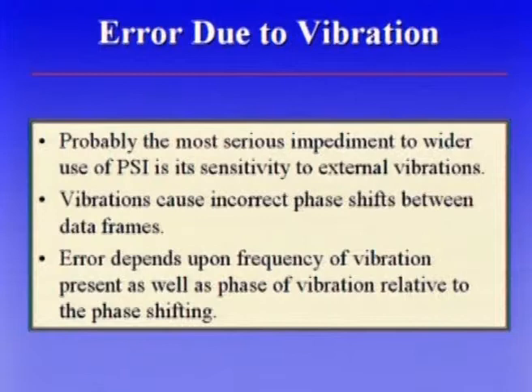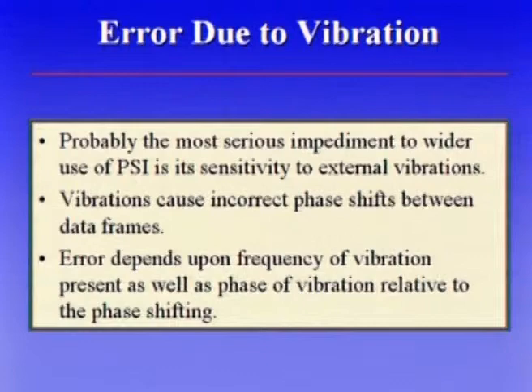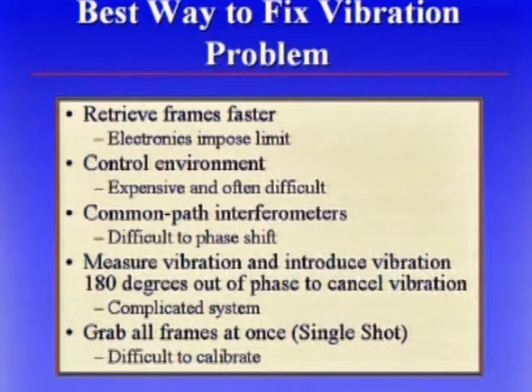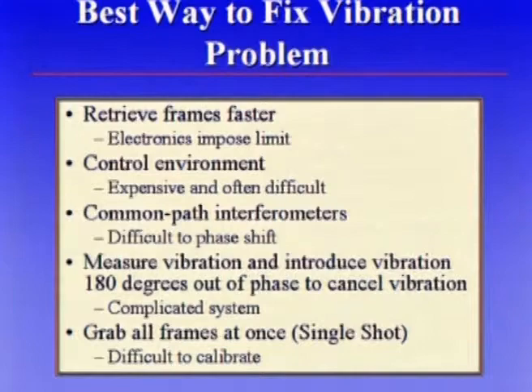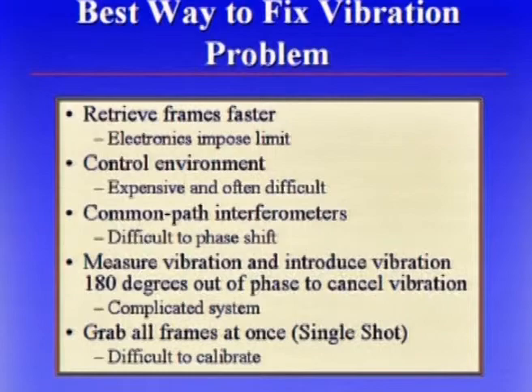Probably the biggest limitation of the use of interferometry is vibration. With vibration present, the results you get are often incorrect. There's a lot of interest in getting around the vibration problem. One way is to take data faster — easier said than done. Another is to control the environment and get rid of vibration — sometimes very difficult. Another is a common path interferometer so both reference and test beams see the same vibration — difficult in many cases. The last approach is to grab all the frames at once — taking three, four, or five frames all at once to freeze the vibration. That is probably the best approach, though there are some calibration problems.